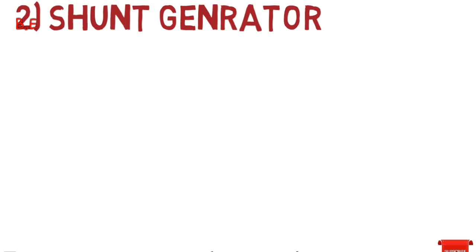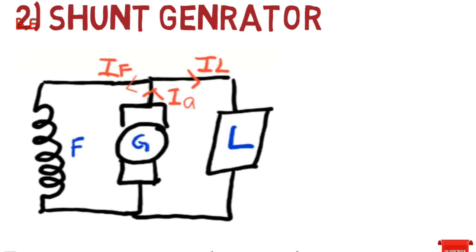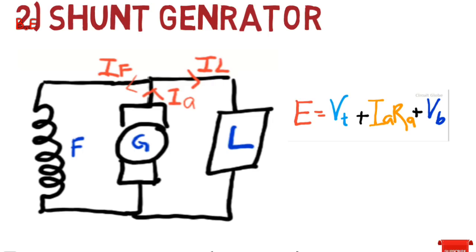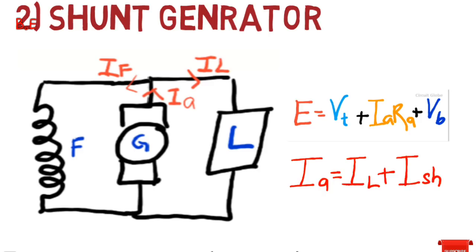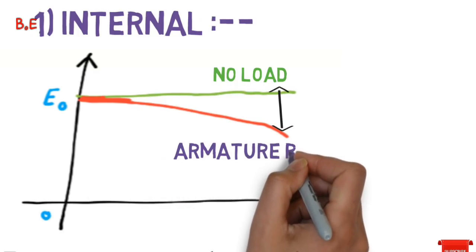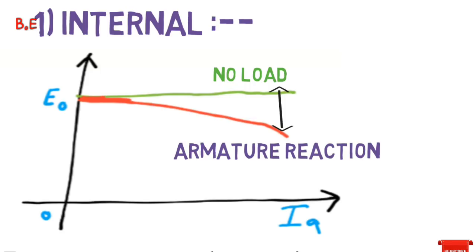Now let's see the performance of a shunt generator. The circuit diagram is shown in the figure. The induced voltage equation is E = VT + IA·RA + VB, and the current equation is: armature current equals load current plus shunt current. If we increase the load, IL increases, resulting in an increase in armature current and losses. The internal characteristic is plotted between induced voltage and armature current, and the difference between no load and on-load induced voltage is due to armature reaction drop — hence induced voltage slightly decreases with increasing armature current.